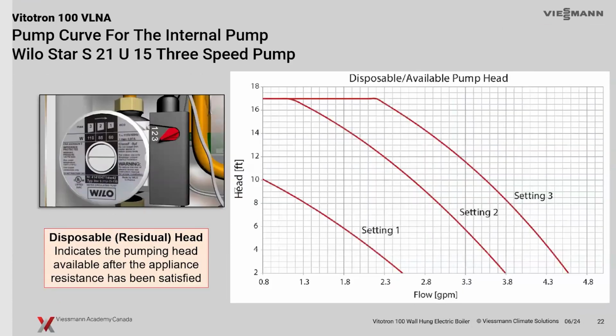And as far as the residual heads, we do have available pump head here. So that built-in pump on speed 3 here, or 2 or 1. You can have a look at what your settings are. I believe it's preset at 3. You can make the adjustments should you want. And your flow rates there, obviously, we're down below 5 gallons a minute here at some pretty low pump heads. So you really want to make sure you do your math on whether or not you want that primary, secondary.